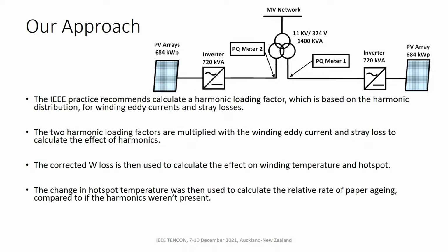So we were starting to look here, first of all, at the IEEE practice. Now, we think the IEEE is maybe just a bit ahead of the IEC standards, because there is one in the IEC for wind generation and transformers connected to turbines, which talks about derating. But it's not across the whole spectrum of transformers, whereas the IEEE practice is more well known. One of the things I do like about it is that for an older transformer, such as on a public distribution network, it might be very hard for the utility to find anything about it, whereas this is easier to apply.